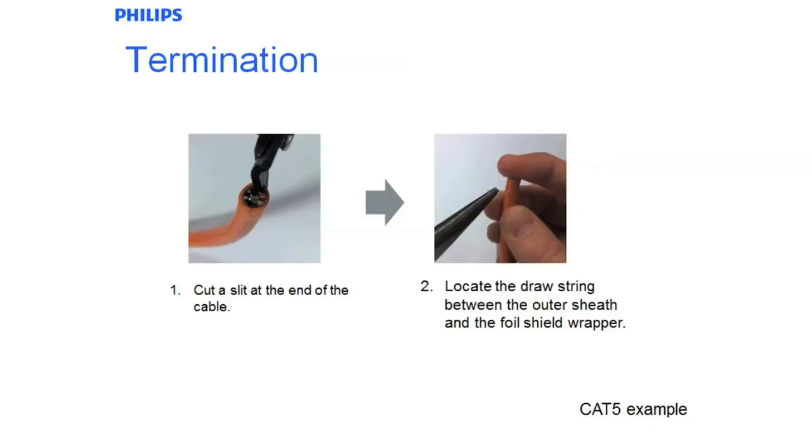Now we will go through the terminations for the typical orange Dynalite Cat5 cable. We cut the slit at one end and strip the cable back. Locate the drawstring which is in between the outer sheath and foil shield wrapper and pull downwards and cut a 90mm snip out of the sheath and then cut away the outer sheath.